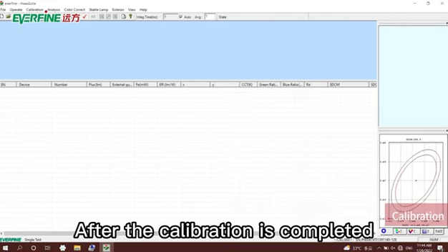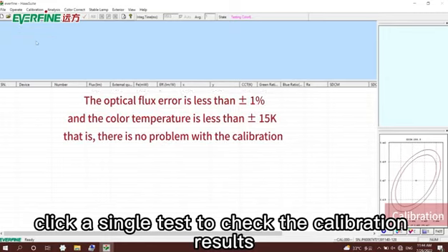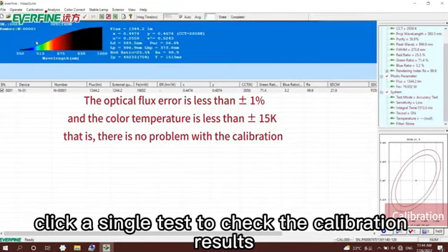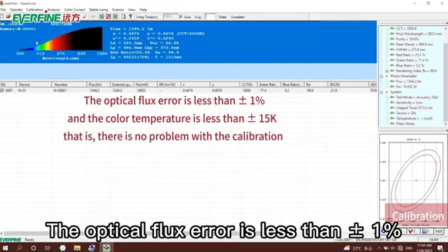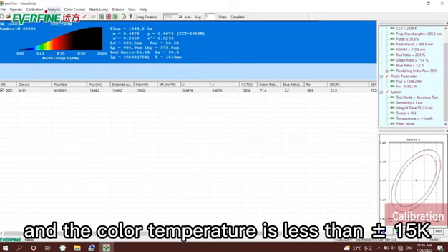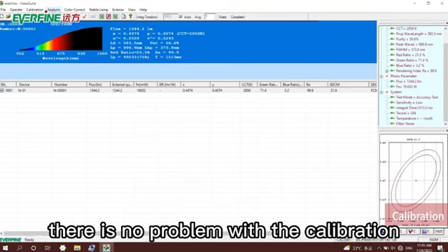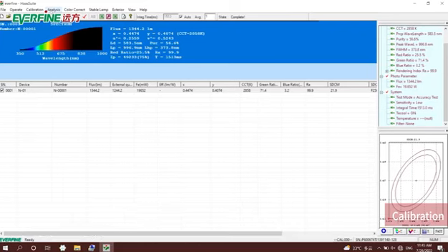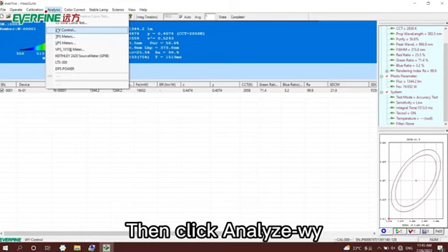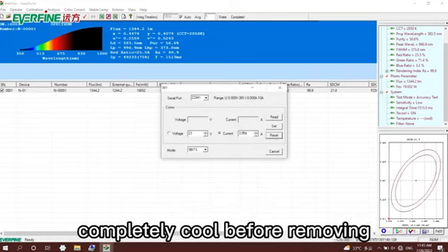After the calibration is completed, click single test to check the calibration results. If the luminous flux error is less than plus or minus 1% and the color temperature error is less than plus or minus 15 K, there is no problem with the calibration. Then click Analyze, and turn off the standard lamp. You need to wait for the standard lamp to cool completely before removing it.